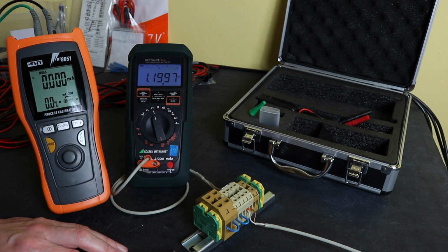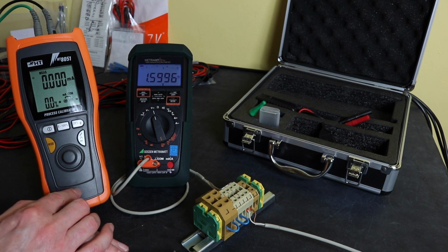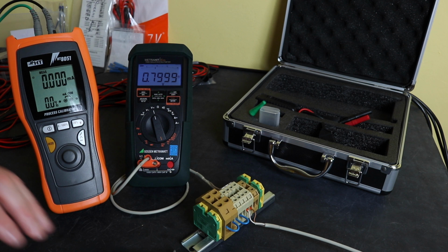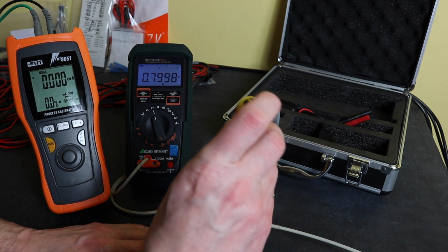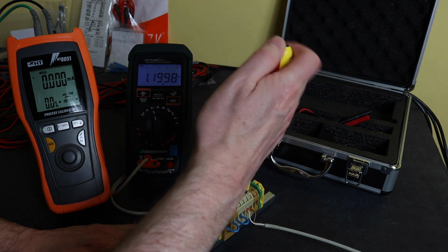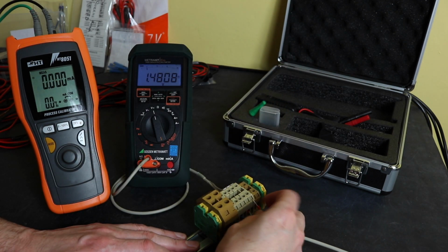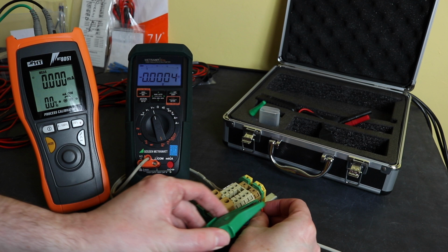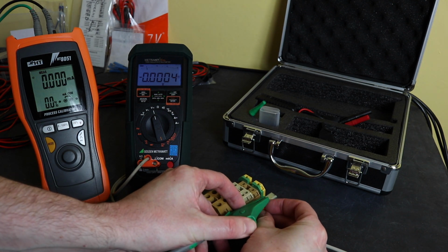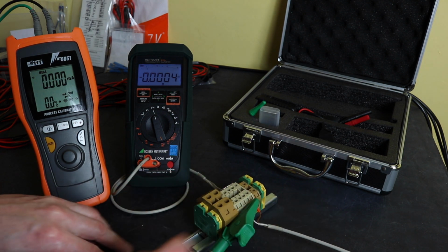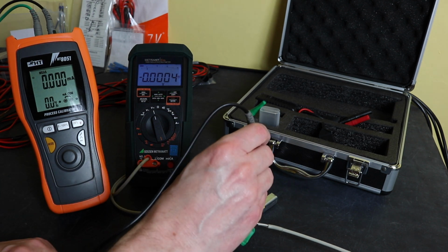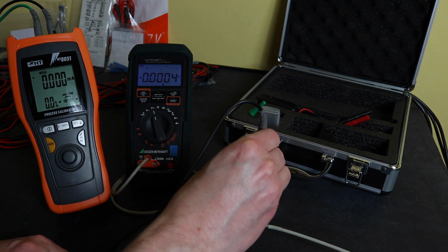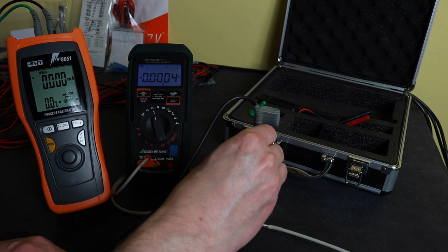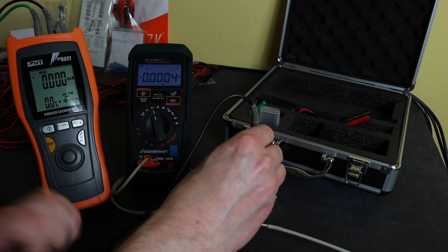If I wanted to check the current coming out of the transducer with the process calibrator, I would need to interrupt this circuit by dropping the wires out on one of these terminals. There's a little wire, I would crocodile clip onto that, and then put my probe in there and remake the circuit in that manner, and then I should get a reading on both.